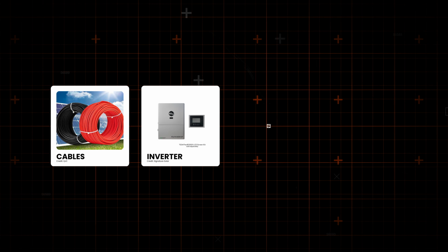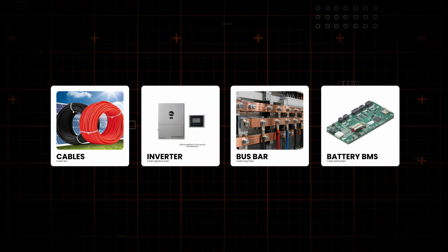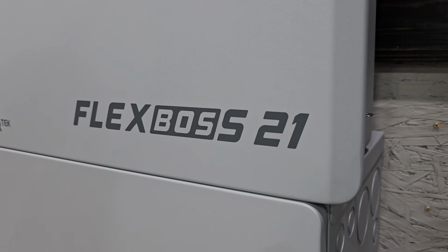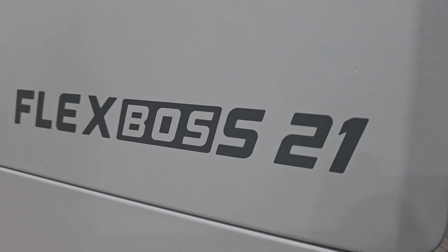Now, that doesn't mean that every battery setup can automatically deliver that. Your battery bank still has to be sized correctly. Your cables, your inverters, your bus bars, and your battery BMS limits, all of that matters a lot. But the inverter itself is built around a pretty capable low voltage battery platform. And that is a part of why people like the 48 volt system. They're familiar. There are a lot of battery options on the market, and they can be easily expanded compared to closed high voltage battery ecosystems. And they can be very cost effective if you're building a large battery backup system.